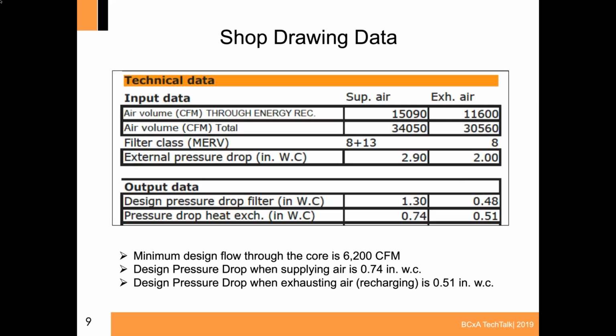So the design data. The important thing here, in the top part of this shop drawing, is that we require a certain amount of supply air coming off of the core, which is our outdoor air ventilation, as well as a specified amount of exhaust air. If you look at the bottom of that snapshot of the shop drawing, you'll see that the pressure drop associated with the supply air coming through should be 0.74 inches water column, and on the exhaust side, 0.51. So the supply air actually does have more volume coming through it and less of the exhaust air going through that. But important here is that the minimum amount on the design going through the core is 6,200 CFM. If you don't have that, you will not get the heat recovery that you're desiring.